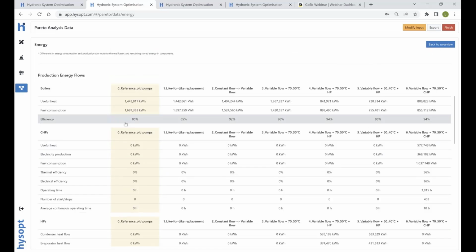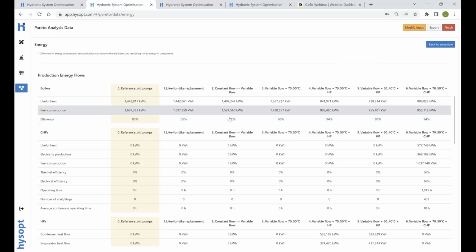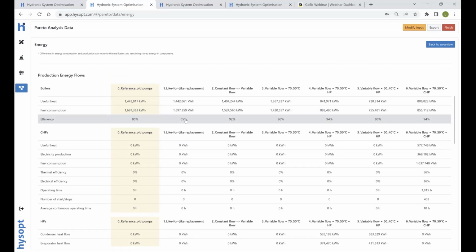Different types of efficiencies, to quickly go through it, as I showed you previously, the condensing boiler efficiency, how it can be increased, and in the like-for-like replacement, why is there no increase in efficiency? They just invested in new condensing boilers.